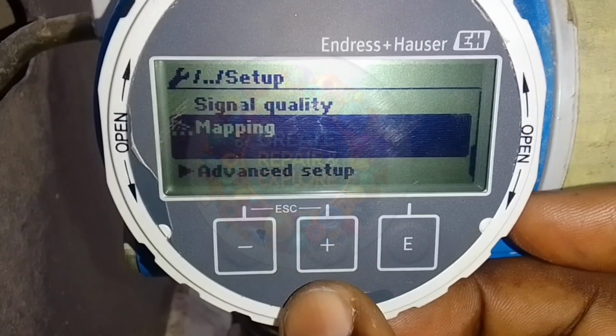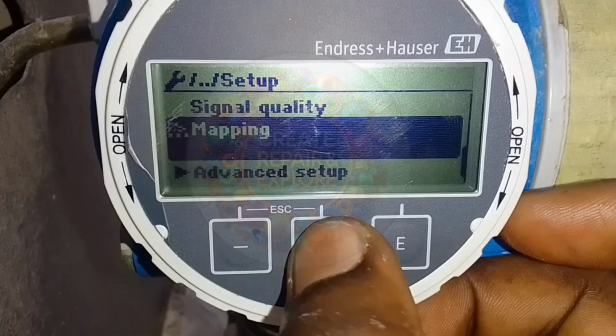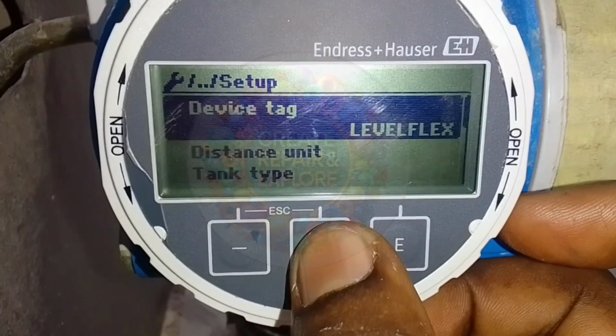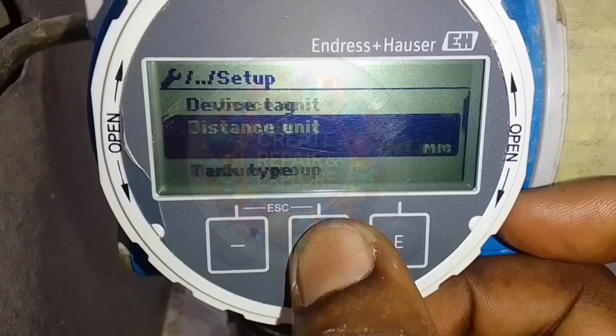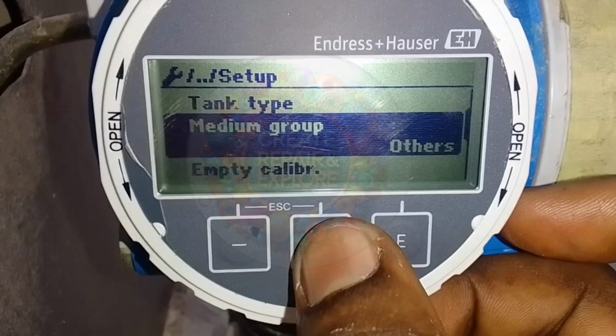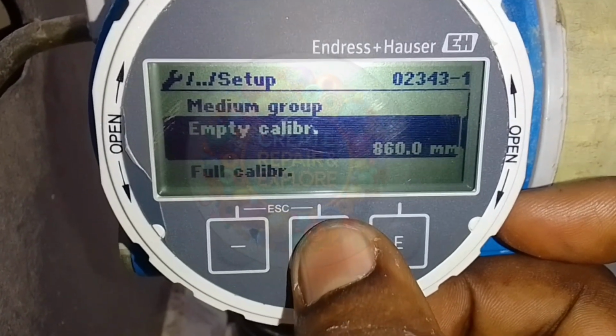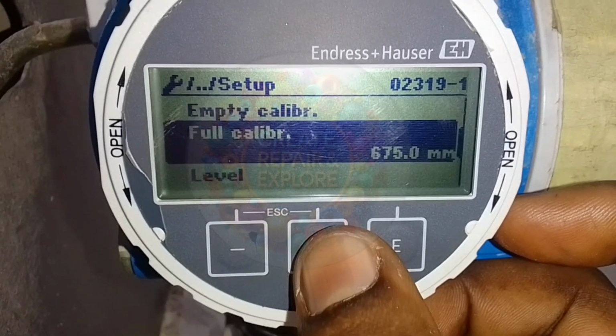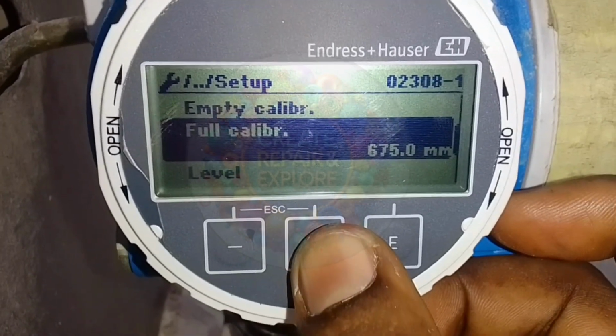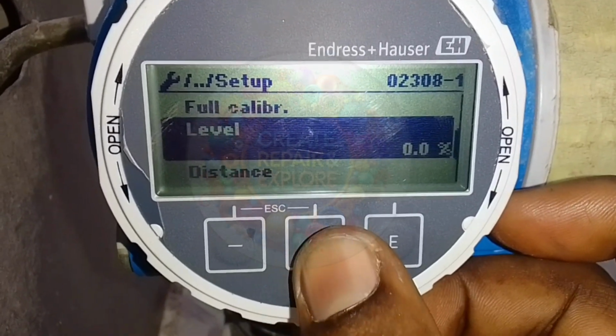So with this, your probe has been calibrated. You can use the plus or minus key to scroll through the parameters to be sure that they are okay. To exit the parameter menu, press the plus and minus key at the same time.